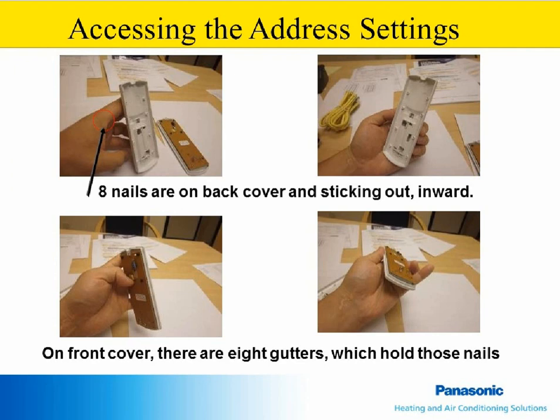If there are multiple indoor units, it is possible to readdress the remote so they can only control one indoor unit. Up to 4 addresses can be used. The exact procedure is in the manual that comes with the indoor unit. As you can see in the pictures, the remote case must be split open to access jumpers that are cut. Our experience has been that many times readdress remotes are lost, misplaced, or mixed up with other remotes. If a readdress remote is used to control another indoor unit, the customer may think that the unit is broke, and this can be difficult to troubleshoot.